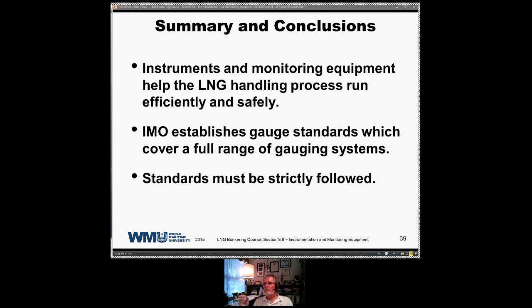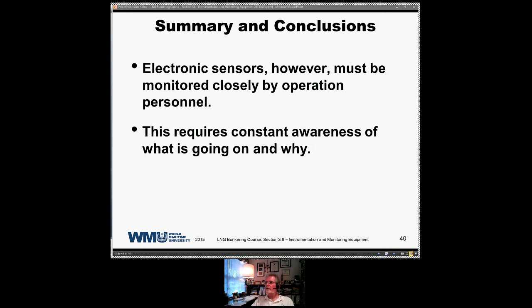Again, safety, environment, safety. The IMO establishes gauge standards which cover a full range of gauging systems, and standards must be strictly followed. Electronic sensors, however, must be monitored closely by operating personnel. All of your monitoring points are monitored automatically and electronically, but this doesn't mean that you can just ignore what's going on. Your operating personnel, your cargo officer, gas engineer, your officers, are constantly in and out of the cargo control area, looking at the various systems, checking.